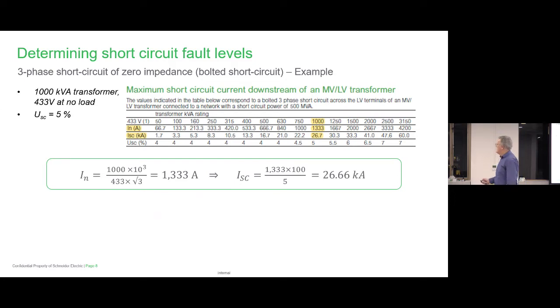Now, I've just also put in here a table that we have in our tech support technical pages in our catalogue, and you can get that in a lot of our catalogues. It's typical, so I'll just go through it. But this is based upon a 3-phase short circuit, bolted short circuit. So when you're starting your network and you're putting in your transformers, you've got 1, 2, 3, whatever. So here I've selected a 1 MVA transformer.